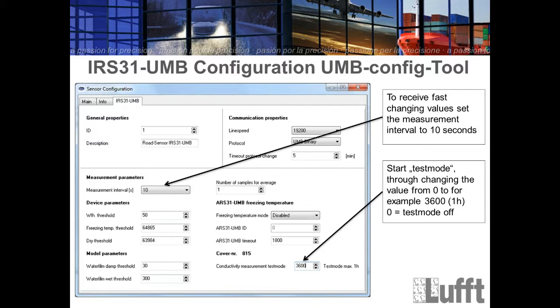And the second thing is the deactivation of the radar. This will be done here with the conductivity measurement test mode. That means start test mode by changing the value from 0, which is the standard value. 0 means the radar sensor is active, to, for example, 3600, which means seconds. 3600 is 1 hour. If you put a value such as 3600 in here, the radar sensor will switch off for 1 hour.